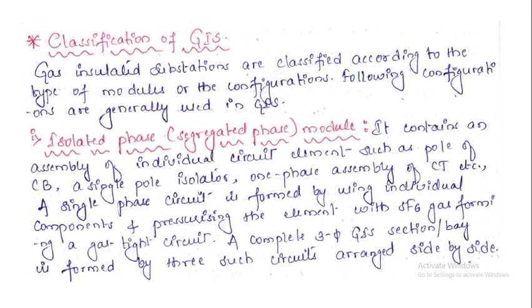Next we'll move on to the classification of the GIS system. The gas insulated substations are classified according to the types of modules and the configurations. The following configurations are generally used in GIS. Isolated phase or the segregated phase modules. It contains an assembly of individual circuit elements such as a pole of a circuit breaker, single pole isolator, one phase assembly of CT. A single phase circuit is formed by using individual components and pressurizing the element with SF6 gas, forming a gas tight circuit. A complete three-phase GIS section bay is formed by three such circuits arranged side by side.